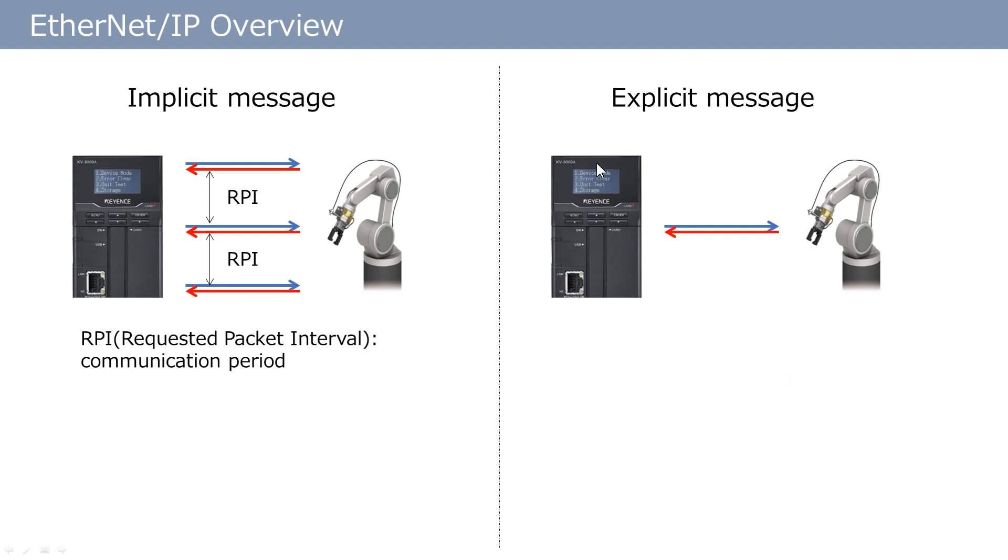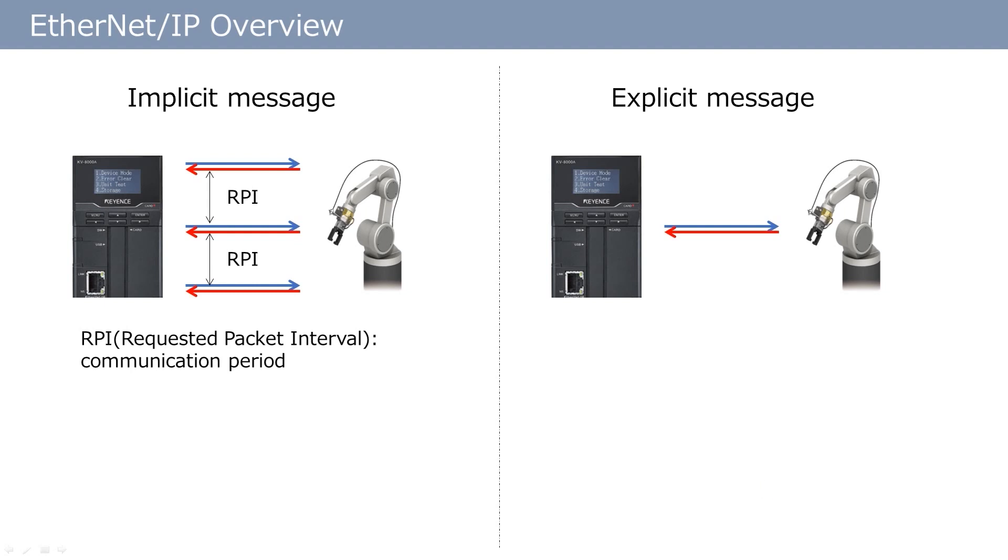Another communication pattern is explicit messaging, where data communication takes place at an arbitrary timing specified by the user. The area, size of the data, and the communicating timing are controlled by a ladder program. Some data cannot be communicated using implicit messages. However, explicit messages can be used for communicating this data. To know what data can be exchanged for each communication pattern, check the manual of the corresponding unit.